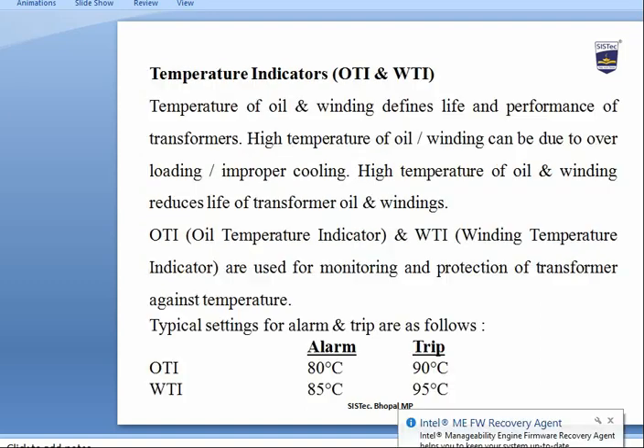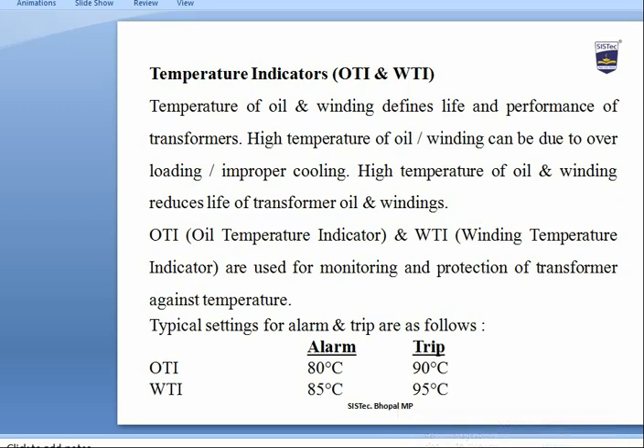OTI stands for Oil Temperature Indicator and WTI stands for Winding Temperature Indicator. Temperature of oil and winding defines the life and performance of the transformer — high temperatures reduce the life of transformer oil and windings. OTI and WTI are used for monitoring and protection against high temperatures. For OTI, the alarm is set at 80°C and the transformer trips at 90°C.